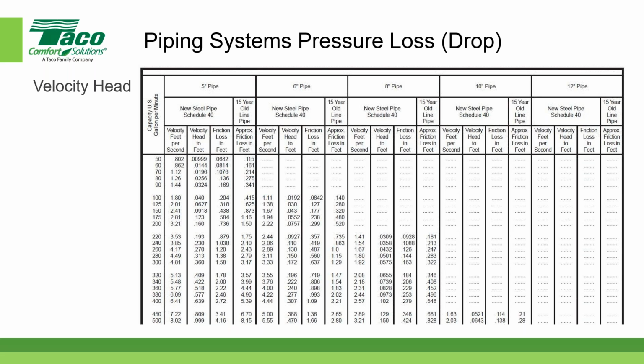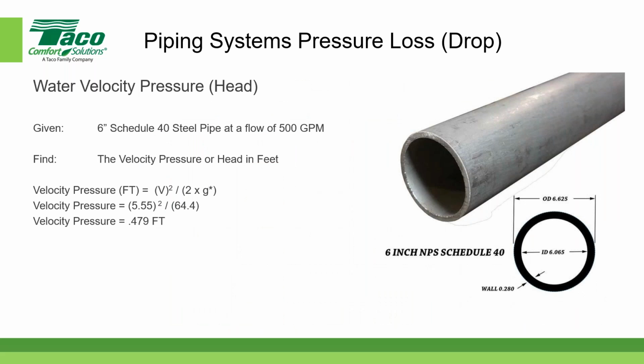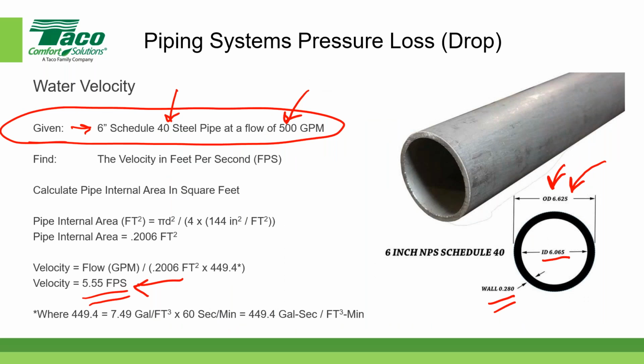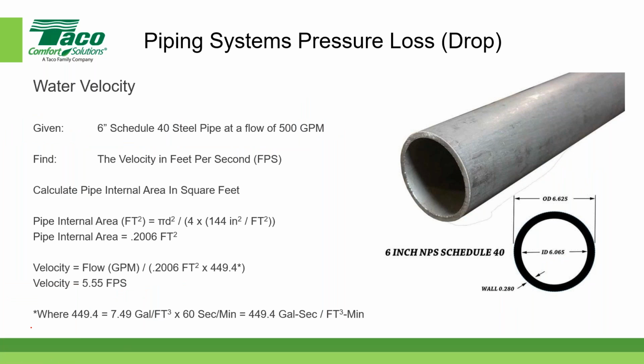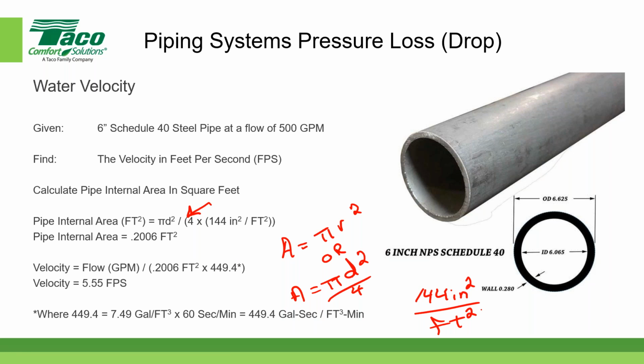And then can you go back a couple of screens to where you showed your first calculation, where you had the area of the circle? Yep. Somebody pointed out the area of a circle is pi times radius squared, and you have pi times diameter squared. Remember, the equation for the area is pi r squared, or if you want to use the diameter, the area is equal to pi d squared over 4. You see the 4 value right there? Yep, there it is. So that's pi d squared over 4. And because the units are in square inches and we want square feet, it's 144 square inches per square foot. We got some people on the ball today. Stanley says but he divided by 4. So we got the mathematicians out there.